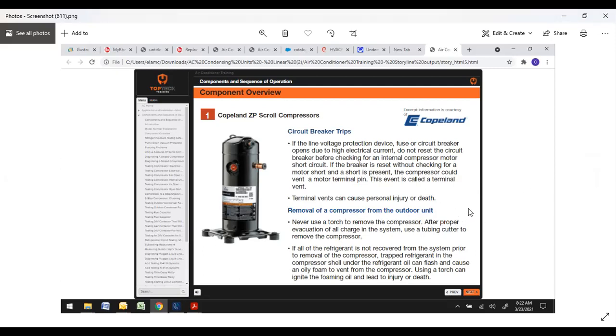This is a big one too. Removal of the compressor from the outdoor unit. Never use a torch to remove the compressor. After proper evacuation of all the charge in the system, it is best to use a tubing cutter to remove the compressor.